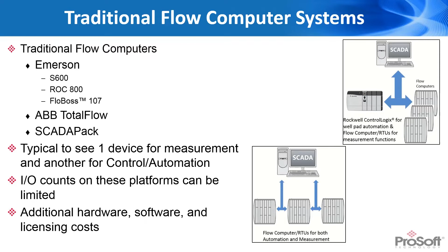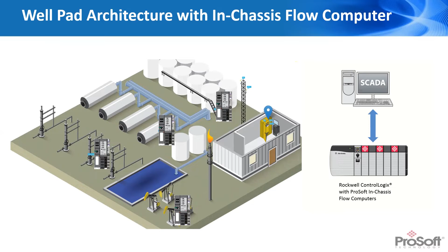So the benefit that you can get by utilizing an in-chassis flow computer is you essentially can bring that all into a single Rockwell-based control architecture. You've got a coprocessor module that essentially fits in the chassis with the controller and performs all of your flow calculations, gives you your measurement-related functions all within a standalone unit, and then additionally allows you to again take advantage of things such as distributed I/O around a well pad site or on a facility.